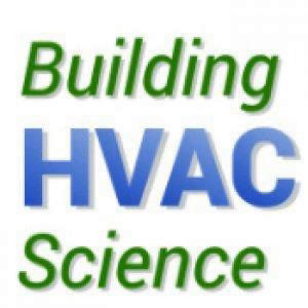When you combine either one of those three smart thermostats with our energy management system, we add features such as excess generation optimization. Again, changing your thermostat based on if you're producing more energy than you're using. Peak demand management. So if you have a peak demand charge in your energy bill, which most commercial customers do, and some residential, again, we could pause or change maybe your thermostat by a degree or two when your oven kicks on. And so we're managing that peak usage. And those are tools that without that real-time energy data, the thermostats cannot offer on their own.